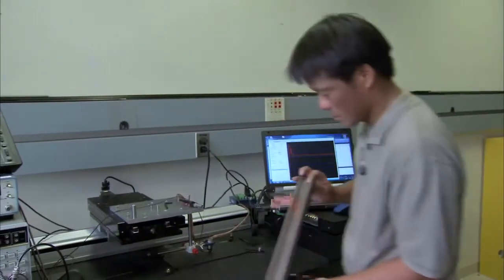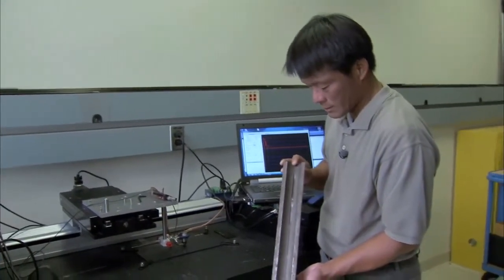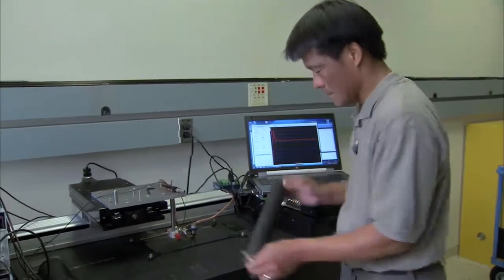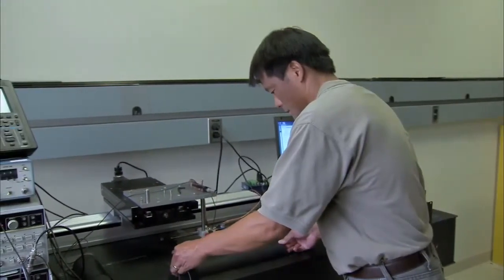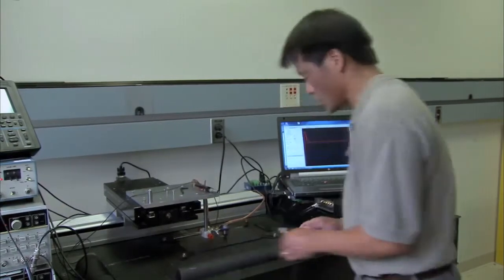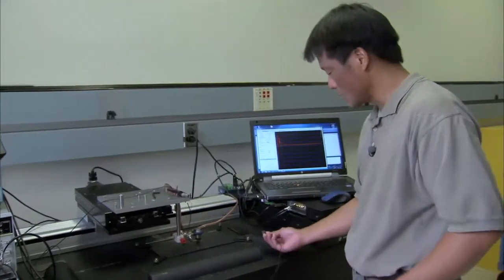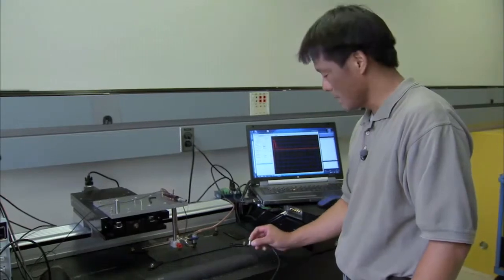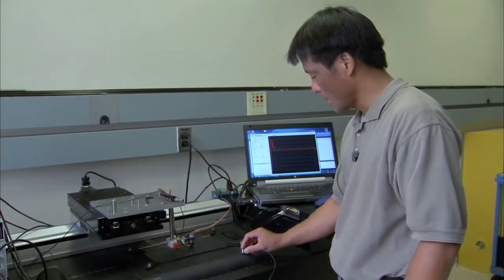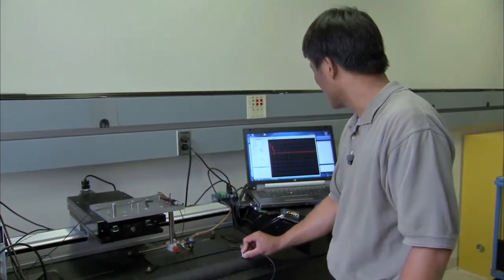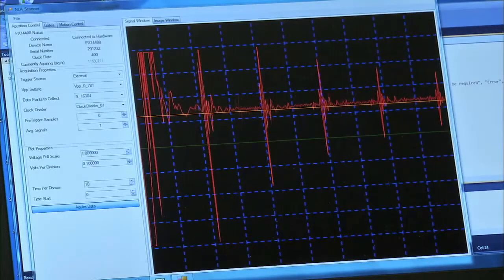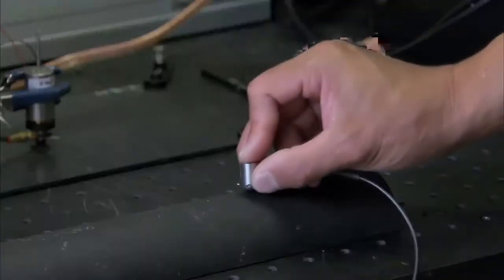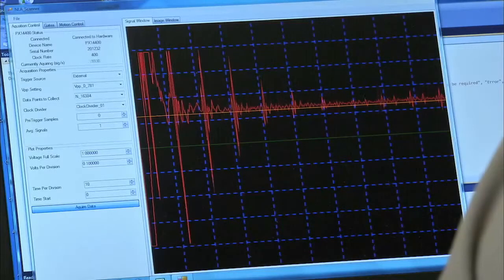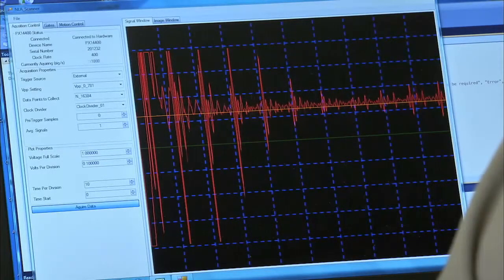Now I want to demonstrate this technology on a pipe with material loss inside, to simulate corrosion damage in the pipe. If we take the transducer and solid couplant material and apply it in an area where there's no defect, you can see again the multiple echoes and the ring down effect. Notice the spacing. If I move the transducer over an area where there's a defect, you can see again the multiple echoes, but they're spaced closer together.